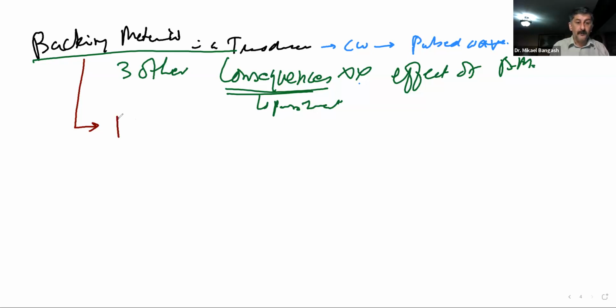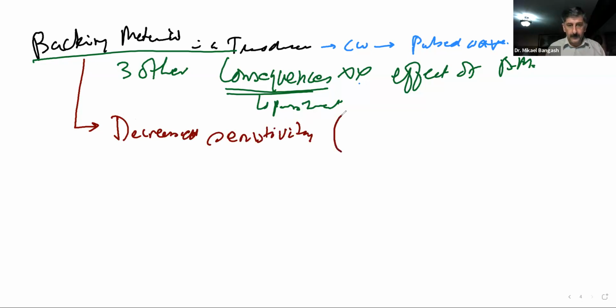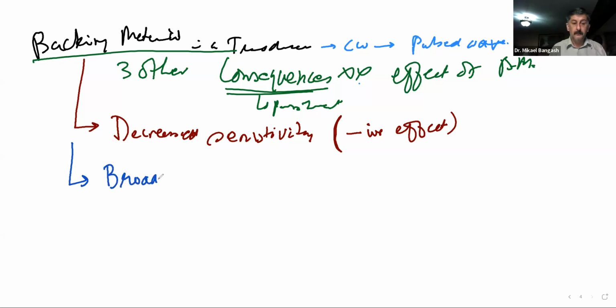Now, one is going to be what we call a decreased sensitivity. Decreased sensitivity. And what can mainly be said about this is that this is going to be a negative effect of adding a backing material to the transducers. Another effect of adding a backing material is that it is going to give the transducer what we can call a broad, or some people may also use the word wide, bandwidth.